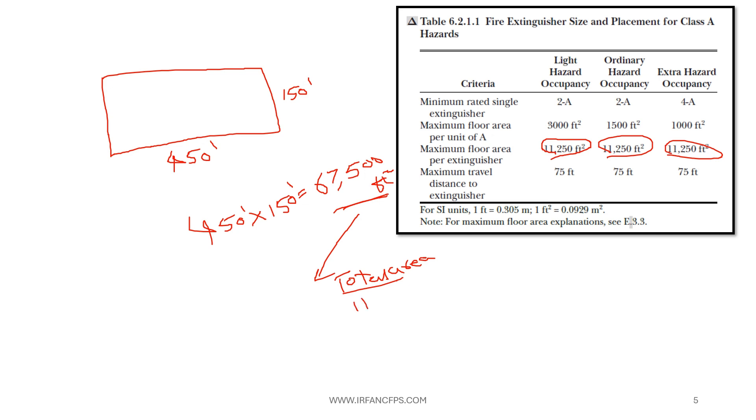So this total area divided by the maximum floor area per extinguisher for any hazard it is 11,250 square feet. So no need to worry about the hazard. So total area 67,500 divided by 11,250. So approximately we are going to get about 6 numbers. So in this way we need to calculate the number of fire extinguishers based on the maximum floor area concept.